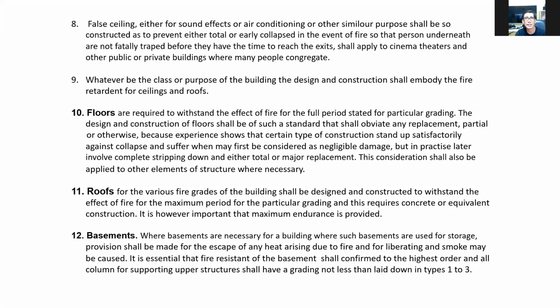So, number 8, 9, 10, 11, 12. Ceilings, either for sound effects or air conditioning or other similar purposes, shall be so constructed as to prevent either totally or early collapse in the event of fire, so that the persons underneath are not fatally trapped before they have the time to reach the exit. This shall apply to cinema theaters and other public buildings or private buildings where many people congregate. No? So it means that you need to make sure that your ceilings or your false ceilings are properly designed to have fire-resistant properties or characteristics. No? So this will protect the people underneath the ceiling.